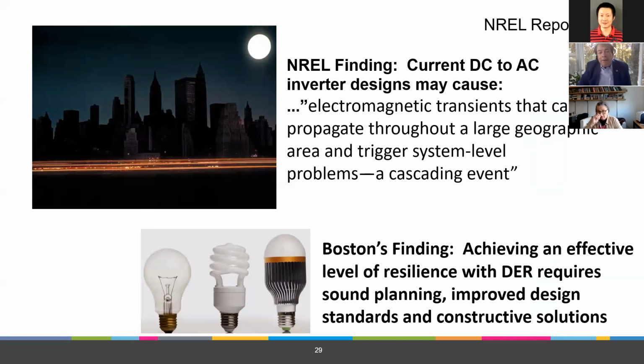Another thing that Dan asked me about before the meeting, which is a little scary to me, was an NREL finding published earlier this year. Electromagnetic transients can propagate throughout a large geographic area given the number of inverters and asynchronous generation that we put on the system, triggering system level problems, and potentially cascading events. This is not acceptable in a design standard, and my finding is we've got to find a way to assure the resiliency of these distributed energy resources.